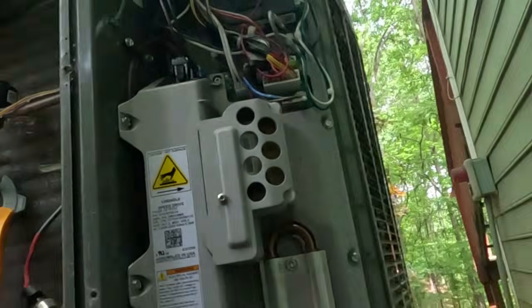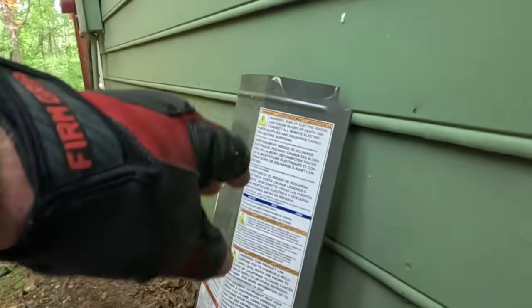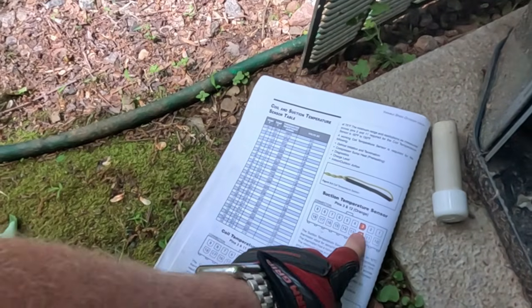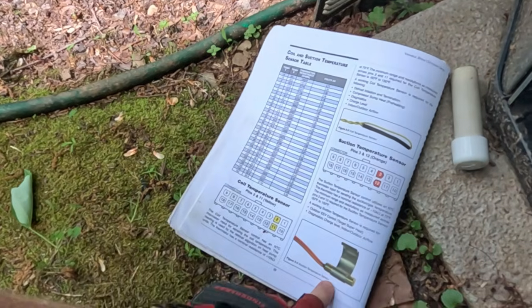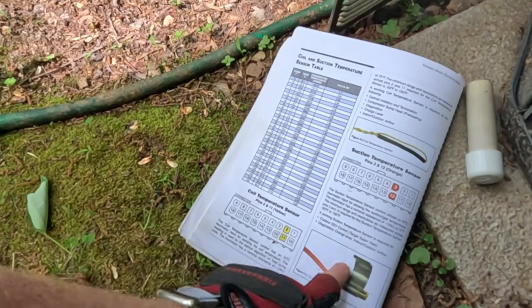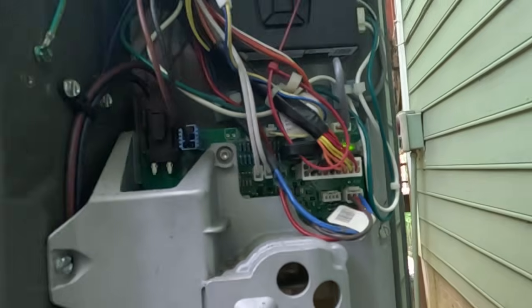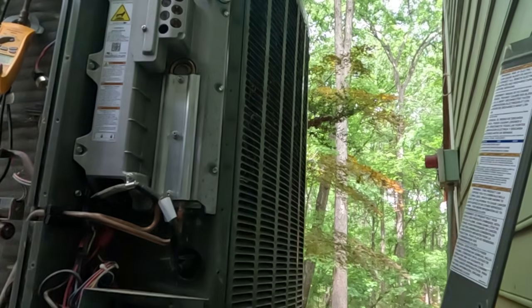Alright, let's get all this checked out. Service facts that usually is in the back of the unit is not there, so I keep the old XV manual on the truck. Suction line temperature sensor right there. Here's the chart for it, so we're going to check that out. These two orange wires right there. Go check our DC voltage, see what it comes out to.